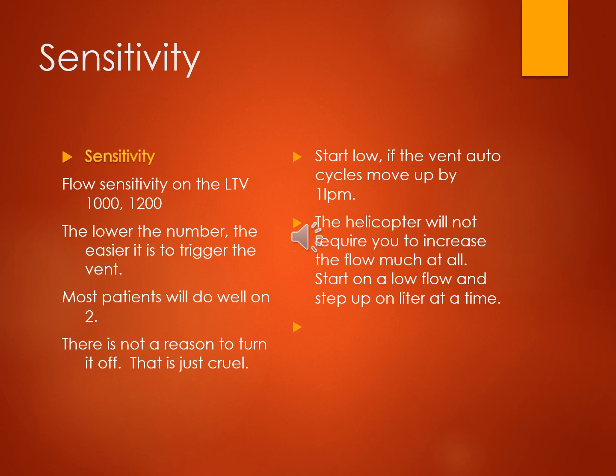It means they have to pull back what would be a liter going through, what that flow would feel like if it was a liter. I guess that's probably the easiest way to understand that. You want the patient to be able to trigger the ventilator, but you don't want to make it so sensitive that it auto cycles with every blow of the wind. You want to adjust that so it's just allowing the patient, when they create a negative flow going through the system, it's enough to trigger that ventilator to take a breath, but not one where it auto cycles.